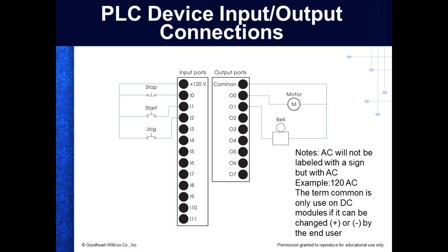Well, no, you're exactly right, but you're also wrong. A solenoid has no contacts on it. But as soon as we put contacts on the end of that big piece of metal, it's no longer called a solenoid. It's called a relay. So you're exactly right. But when we use the term solenoid, it's just a linear actuator. But a relay is a combination of a what? Solenoid and a switch. That's exactly right. And so a solenoid has a different symbol, right? It's got that up-shaped symbol, kind of like a cut-off resistor, but it only has one up and one down.